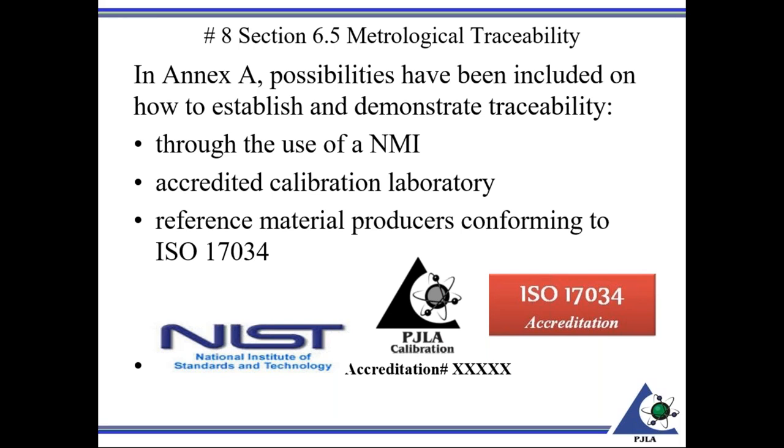In 17025, we have some guidance in Annex A on how to demonstrate traceability. So this is basically your measuring devices. When you're measuring something, you have equipment to measure, say, temperature, or frequency, whatever it happens to be. It could be a balance. In a testing laboratory, an analytical type balance.